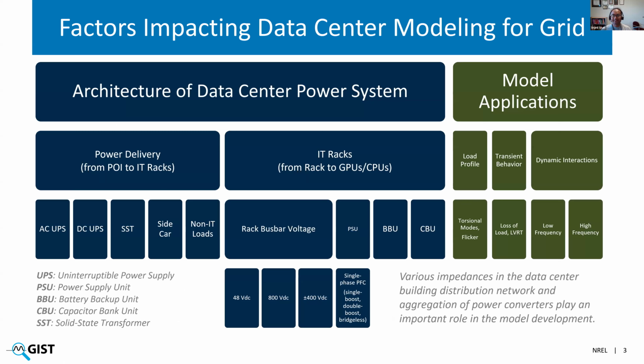In terms of factors that influence data center modeling, one is model application: what do you want to use this model for? Is it just the load profile, which has been the topic of many previous presentations, to understand its impact on issues like torsional oscillations in nearby generators or flicker? Are you looking at transient behavior, loss of load, LVRT ride-through, or also dynamic interactions like oscillations, weak grid stability issues, control interactions? Depending on the objective, the model can look very different. You can make a lot of simplifications if focusing on a narrow type of study, but if you want a model that can be used for all these things, it can be very complicated.